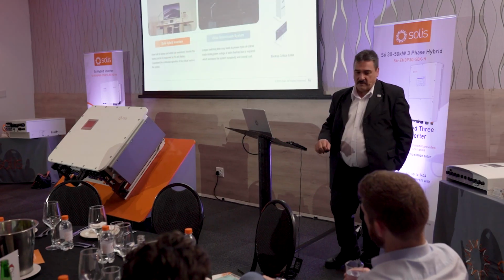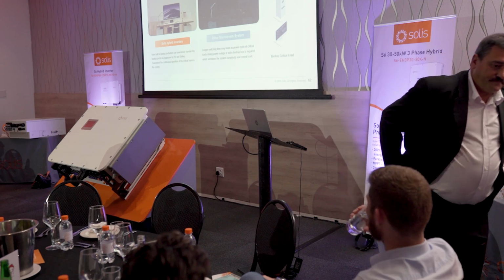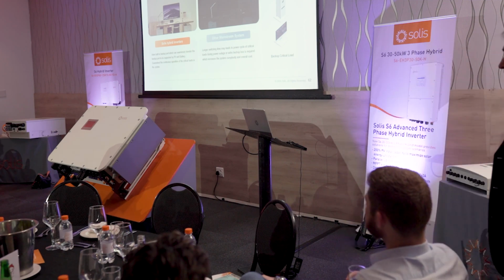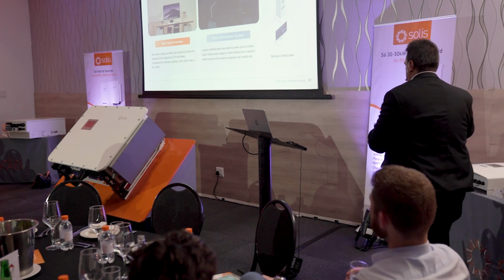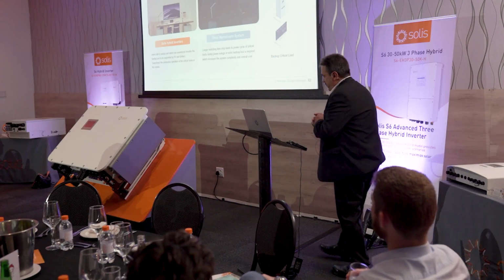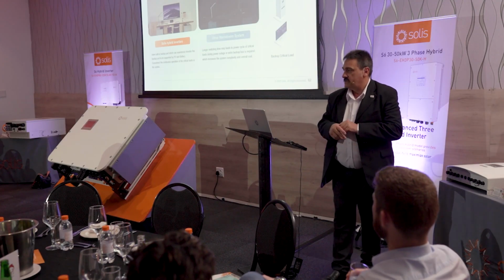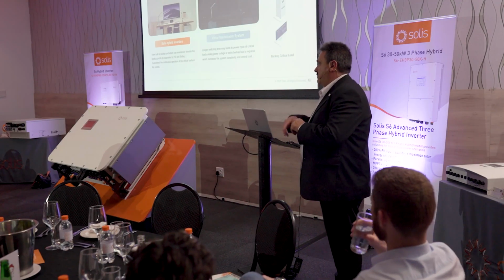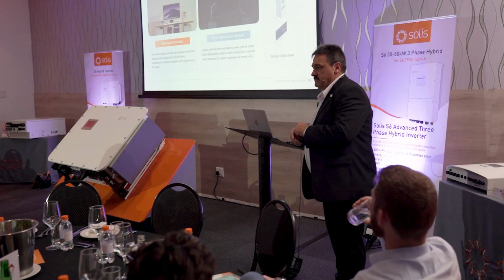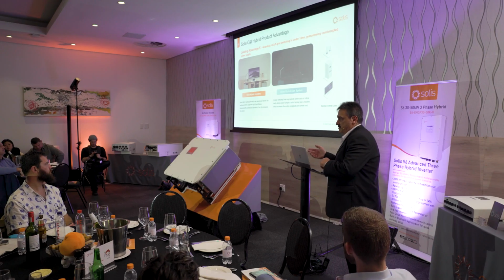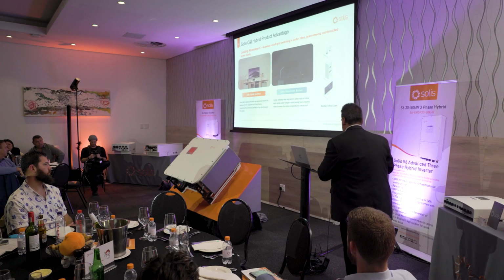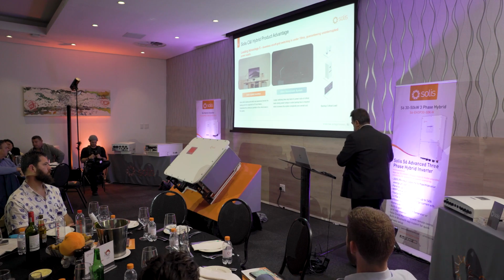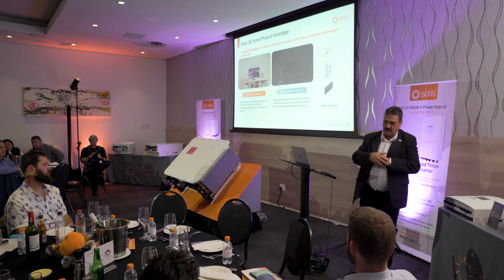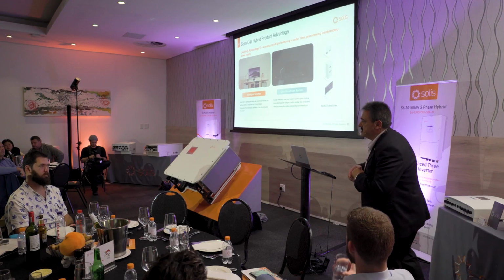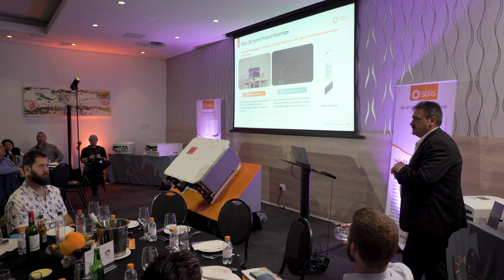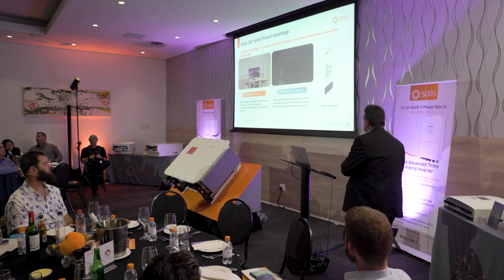Okay, so we come to changeover times. Up to 6 inverters in parallel, we have a changeover time to the backup port completely in less than 10 milliseconds. We do about 4 milliseconds on a residential product. So 10 milliseconds up to 6 inverters. After that, the STS will allow you up to 10 inverters, but pretty much a UPS switchover function. Okay, it's really quick.